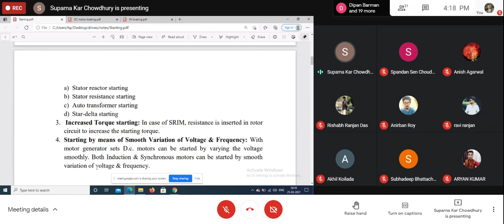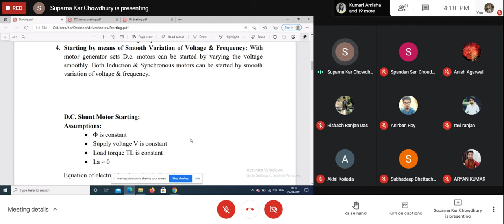Here, both voltage and frequency have to be varied because if we only vary the voltage, keeping the frequency constant, flux will change, so that will change the characteristic and operation of the motor. So to keep the flux constant, we change the voltage and frequency, that is V by F ratio remains constant. So V by F controller is very widely used for AC motors, both induction and synchronous.